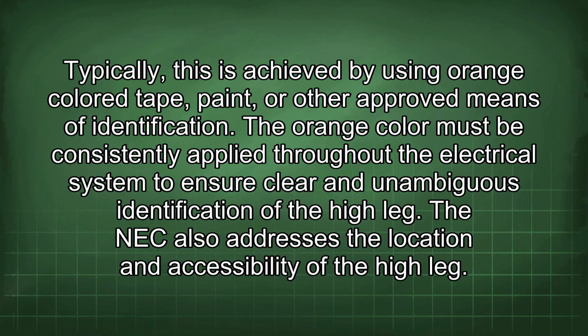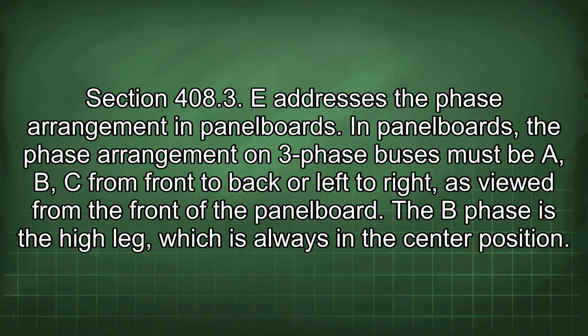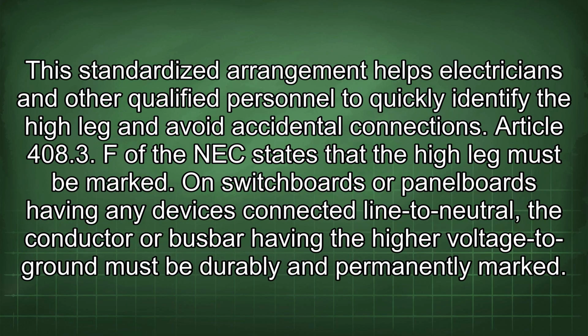The NEC also addresses the location and accessibility of the high leg. Section 408.3(E) addresses the phase arrangement in panel boards. In panel boards, the phase arrangement on 3-phase buses must be A, B, C from front to back or left to right, as viewed from the front of the panel board. The B phase is the high leg, which is always in the center position. This standardized arrangement helps electricians and other qualified personnel to quickly identify the high leg and avoid accidental connections.